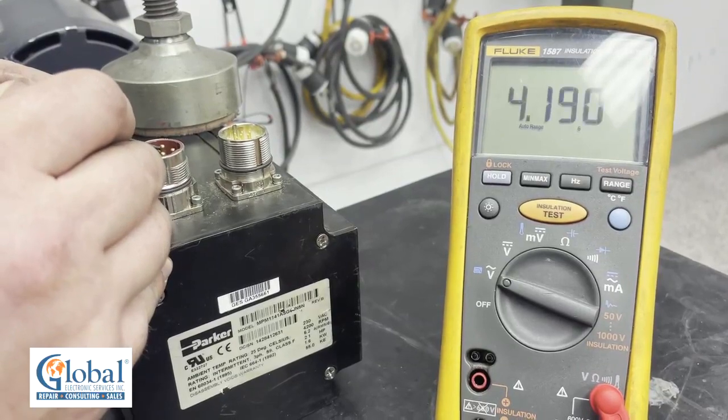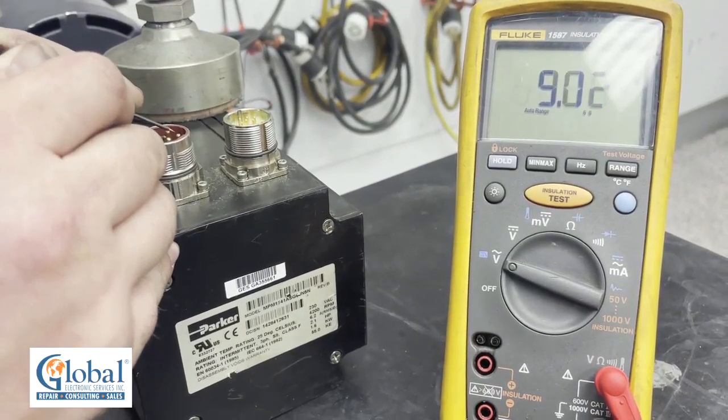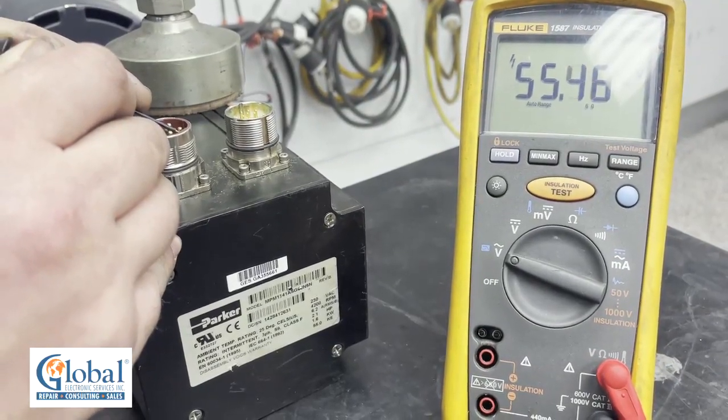Now we will test the U to W — and again it's 55 megohms. And now to test the V to W, also coming out at 55 megohms.